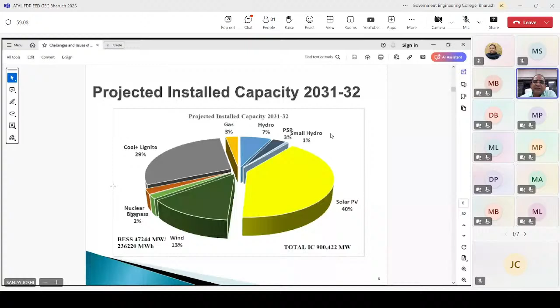Energy calculation is also very important. Installed capacity does not mean that all installed generators have plant load factor equal to 100%. That is not the case. So let me give a sample calculation: 100 gigawatt installed capacity, 24 hours, 365 days. So annual energy production for 100 gigawatt, if running round the clock for the whole year, will be 876 billion units.